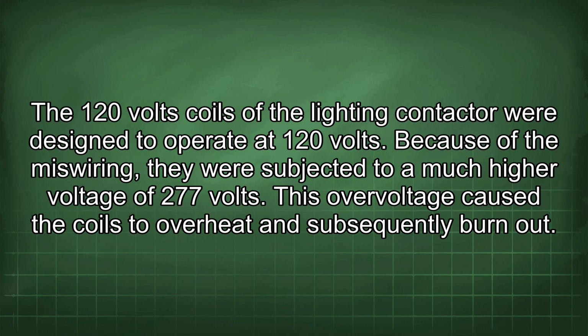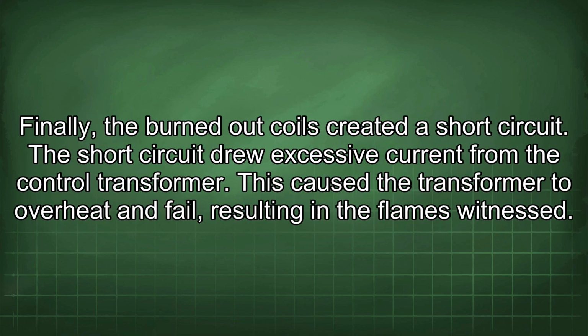The 120 volts coils of the lighting contactor were designed to operate at 120 volts. Because of the miswiring, they were subjected to a much higher voltage of 277 volts. This overvoltage caused the coils to overheat and subsequently burn out. Finally, the burned out coils created a short circuit. This short circuit drew excessive current from the control transformer. This caused the transformer to overheat and fail, resulting in the flames witnessed.